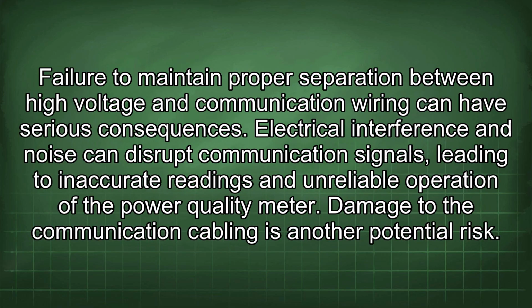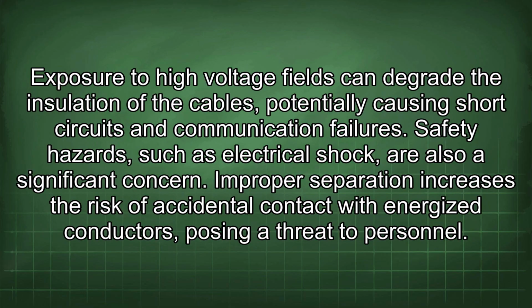Failure to maintain proper separation between high voltage and communication wiring can have serious consequences. Electrical interference and noise can disrupt communication signals, leading to inaccurate readings and unreliable operation of the power quality meter. Damage to the communication cabling is another potential risk. Exposure to high voltage fields can degrade the insulation of the cables, potentially causing short circuits and communication failures. Safety hazards, such as electrical shock, are also a significant concern. Improper separation increases the risk of accidental contact with energized conductors, posing a threat to personnel.